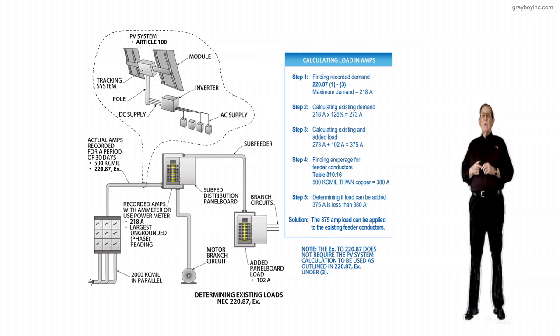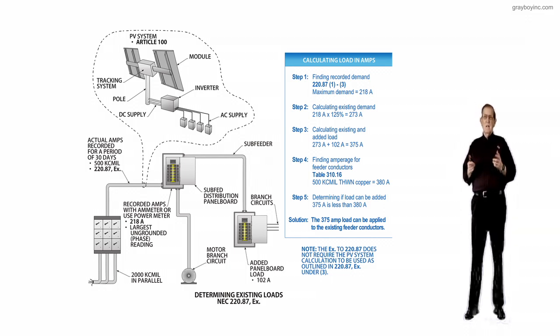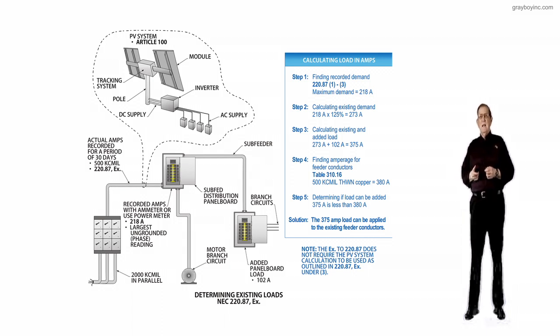One other thing I would call out, where the authority having jurisdiction feels like it's been done properly: if we look at 310.14(A)(1), the engineer may calculate the ampacity of these conductors without using Table 310.16 by following the rules of 310.14(A) there.